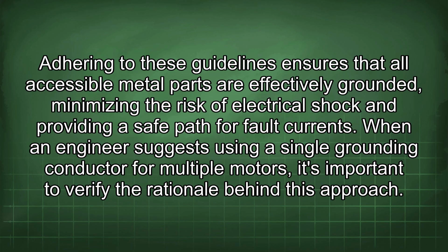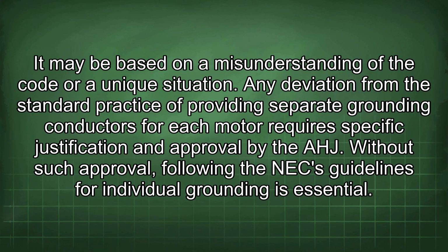When an engineer suggests using a single grounding conductor for multiple motors, it's important to verify the rationale behind this approach. It may be based on a misunderstanding of the code or a unique situation. Any deviation from the standard practice of providing separate grounding conductors for each motor requires specific justification and approval by the AHJ. Without such approval, following the NEC guidelines for individual grounding is essential.